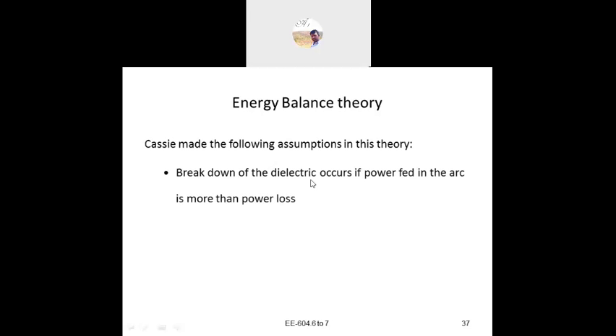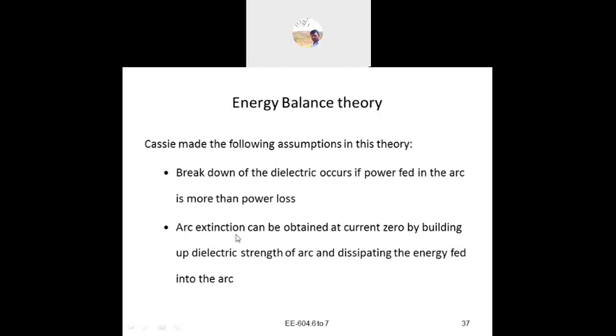Next, the energy balance theory. It rests on the following assumption: breakdown of the dielectric occurs if the power fed to the arc is more than the power loss. Arc extinction can be obtained at current zero by building up the dielectric strength of the arc and dissipating the energy fed to the arc.